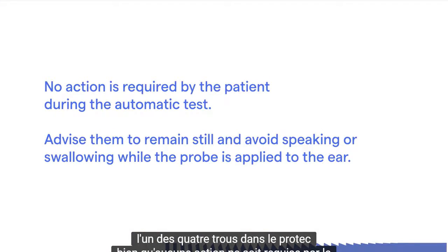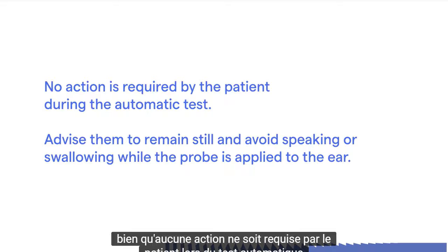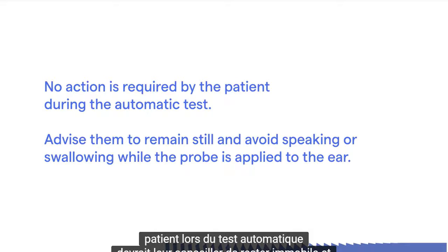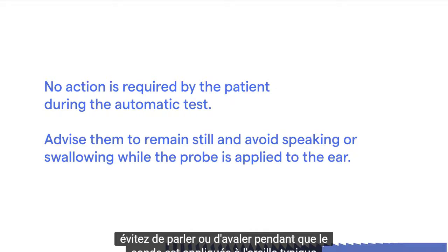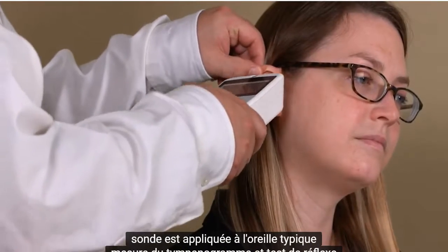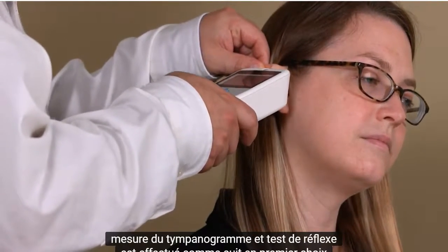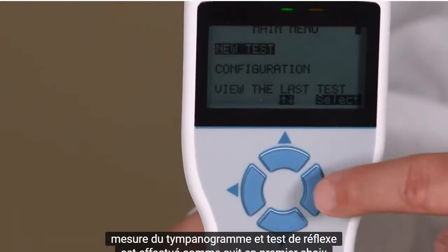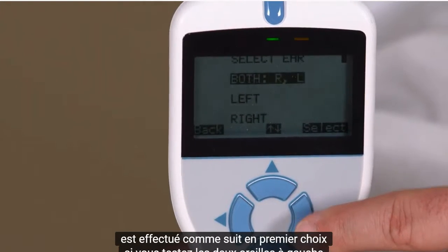Although no action is required by the patient during the automatic test, you should advise them to remain still and avoid speaking or swallowing while the probe is applied to the ear. A typical tympanogram measurement and reflex test is carried out as follows. First, select if you are testing both ears, the left ear only, or the right ear only.